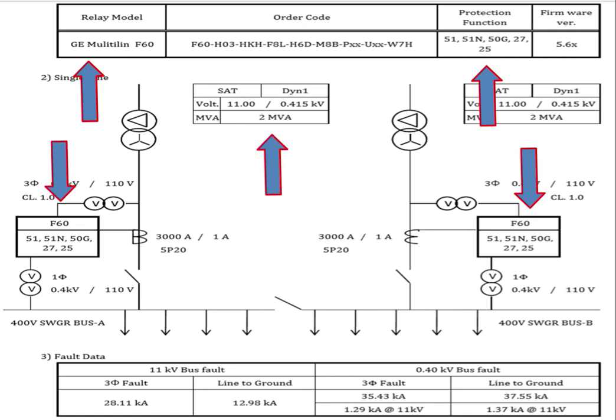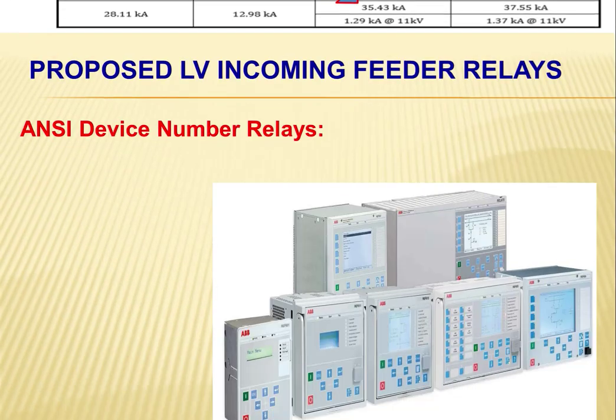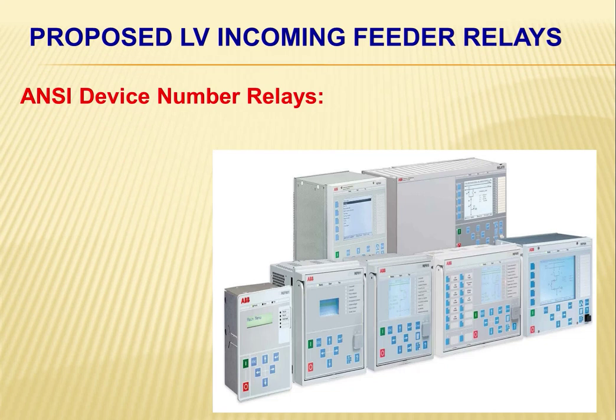Okay, and our transformer is rated 2 MVA, and we have also our three-phase fault, which is rated 35.43 kiloamperes. We're going to utilize this when we calculate our TDM or time dial multiplier. So these are the 5 relays that we're going to use for our discussion.